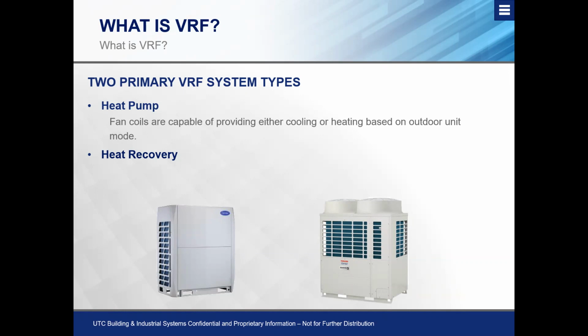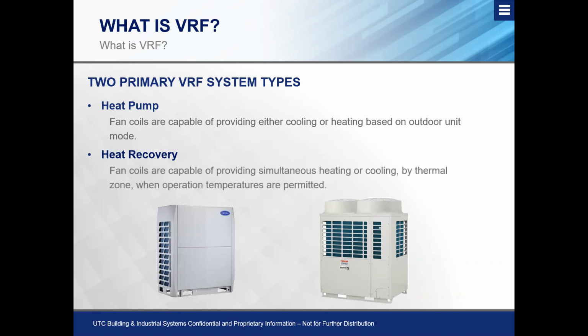And then switching over to heat recovery, which VRF is most notably known for, is the simultaneous heating and cooling. So we allow the fan coils on the indoor unit to provide simultaneous heating and cooling by thermal zone when operation temperatures permit. And essentially what that means in a nutshell is we can have one unit of heat, one unit of cooling, and we'll get into how that's possible very shortly. But it's important to understand that both of our systems, the Carrier and the Toshiba Carrier, have a heat pump and/or a heat recovery option.